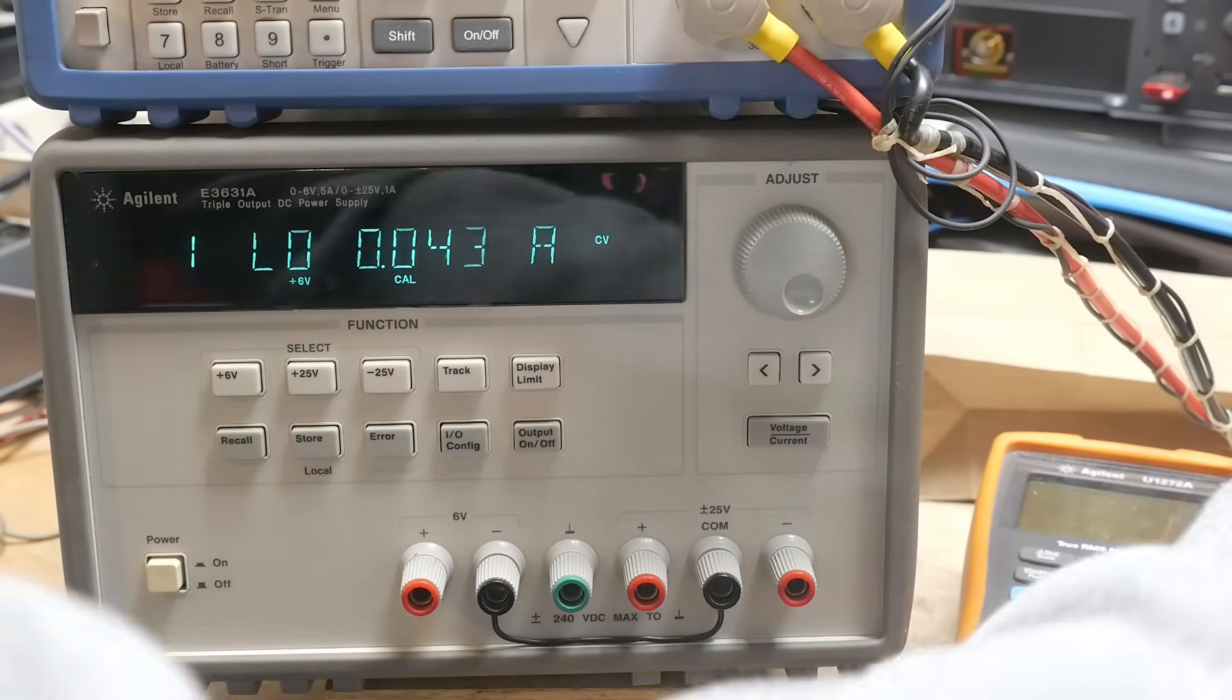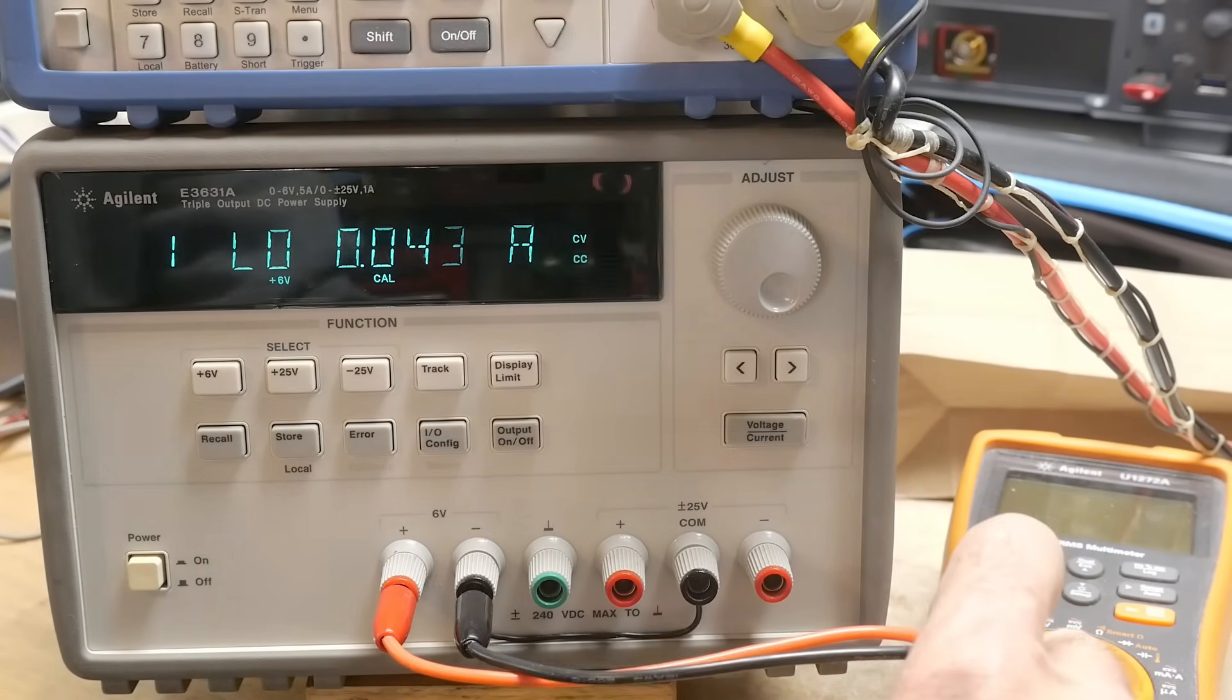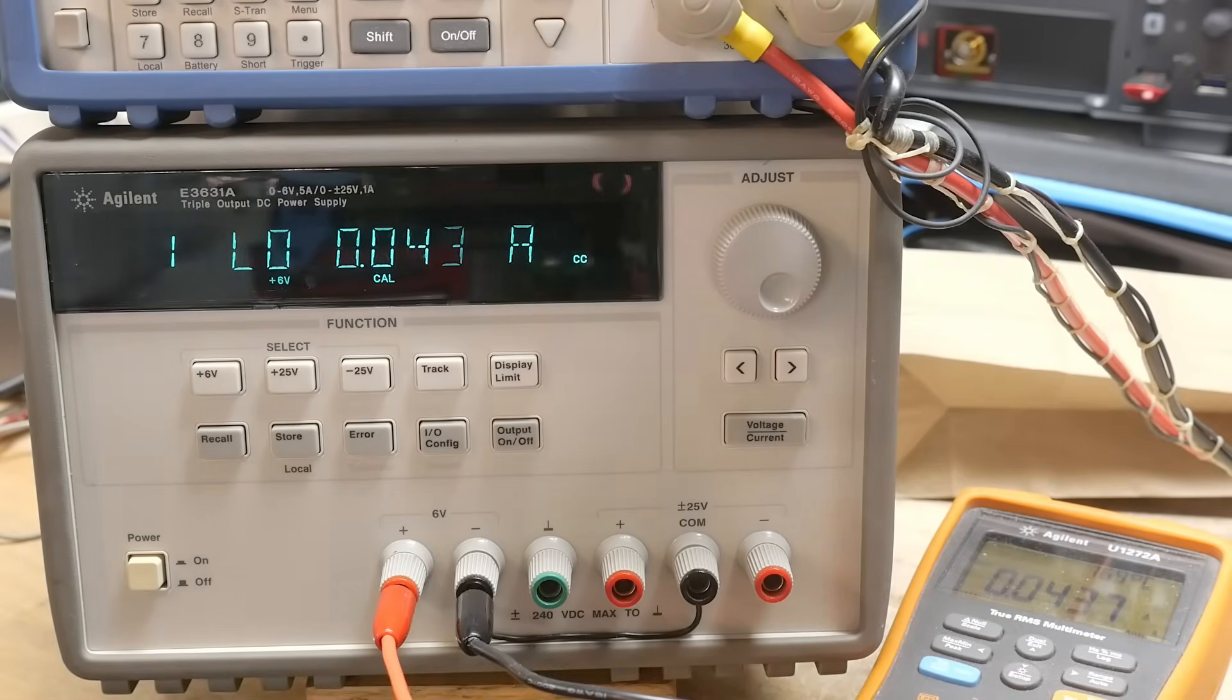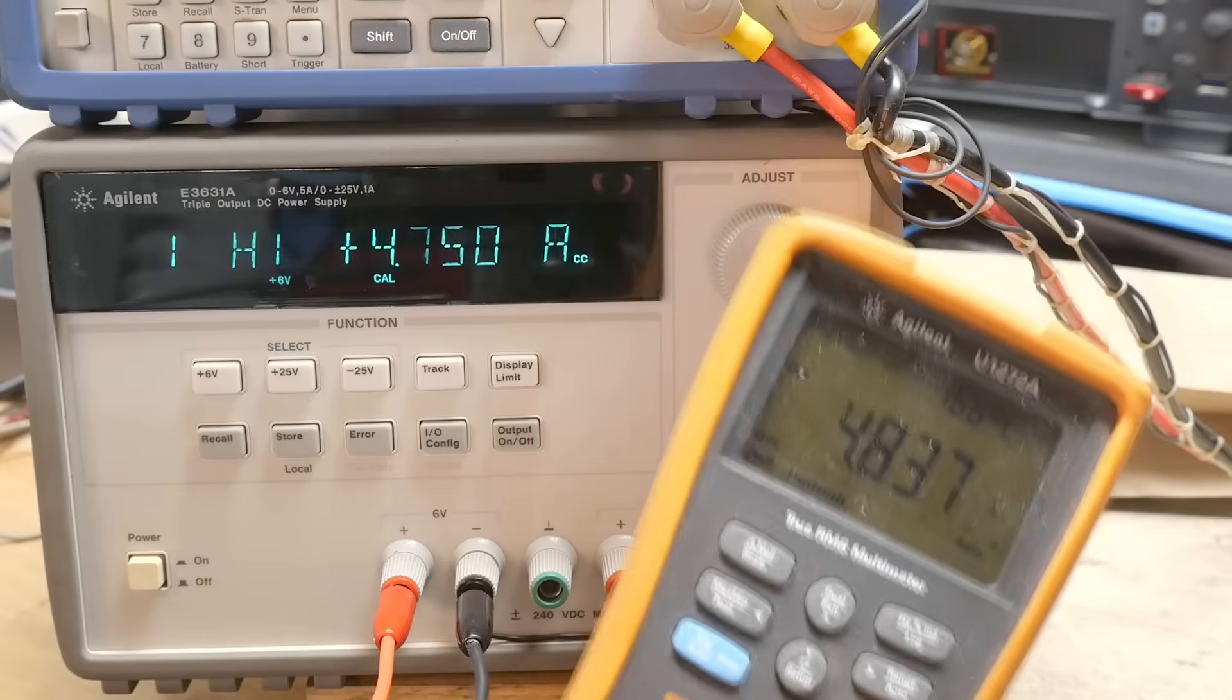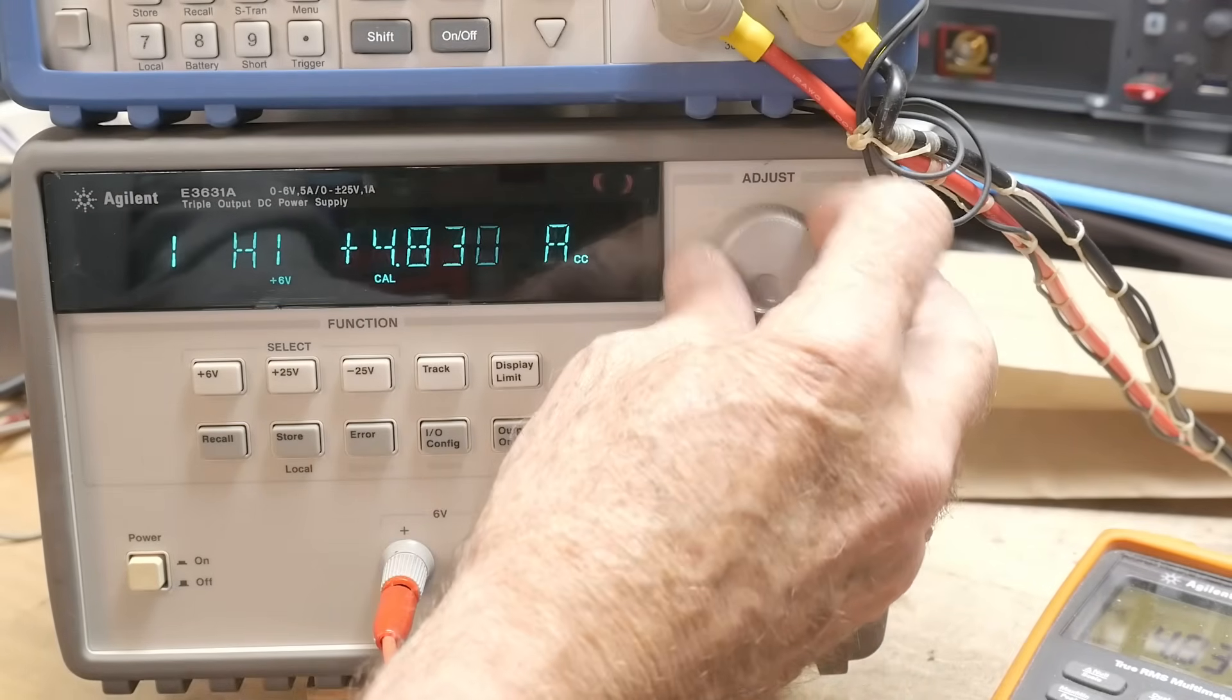So we're going to have to disconnect this and we will hook up a meter here that can do 10 amps. So I've got that hooked up. So we will hit enter. Now it's outputting 4.75 amps and we're outputting this number here, 837. So we're actually outputting that number there. So now we're doing CAL3.